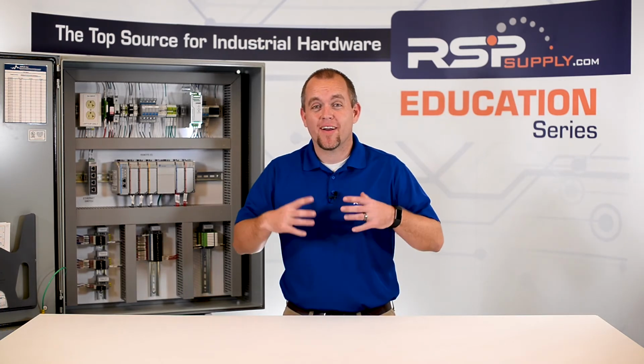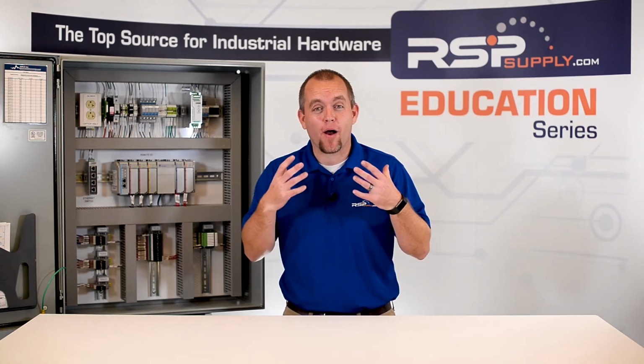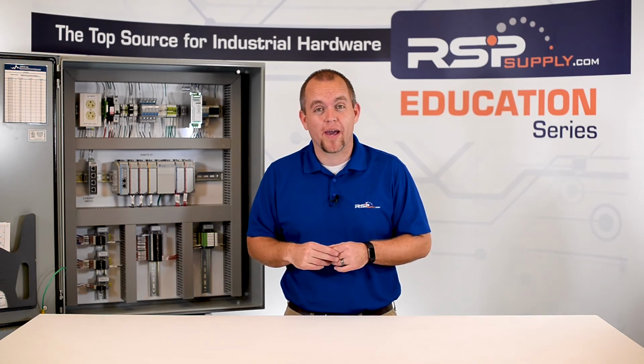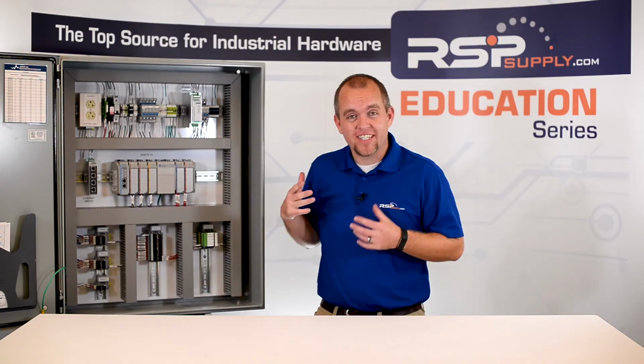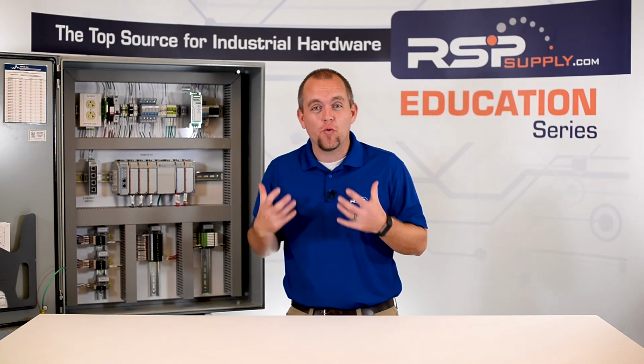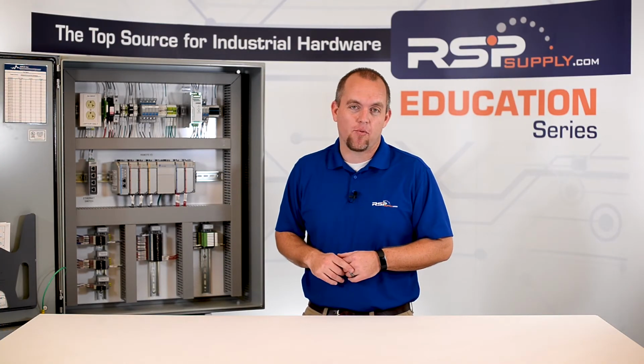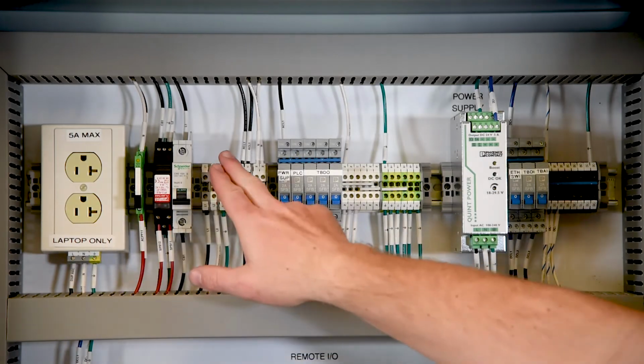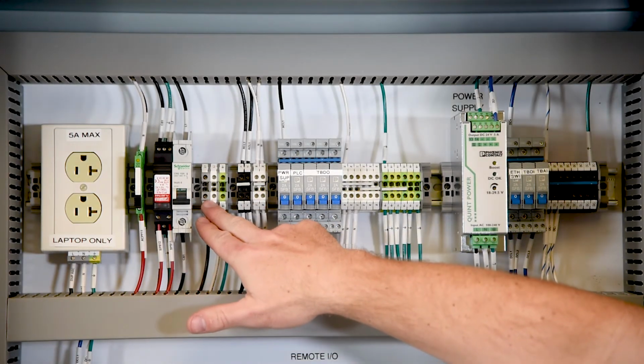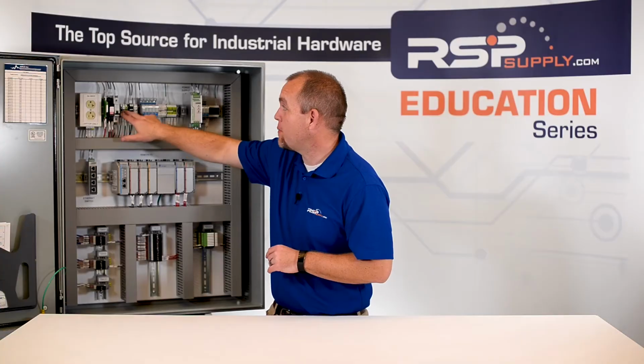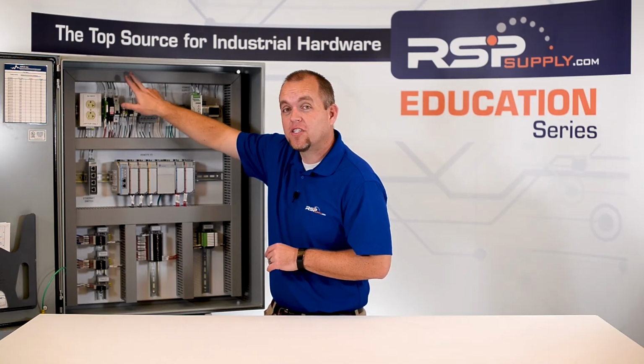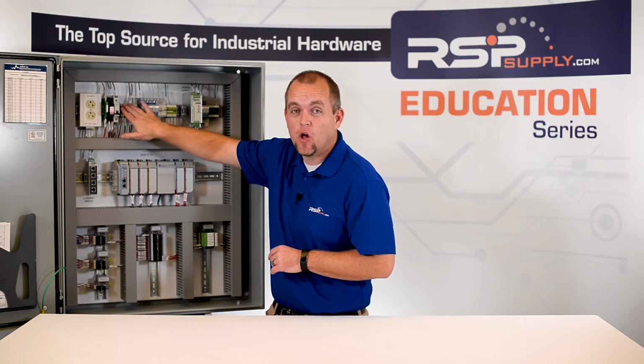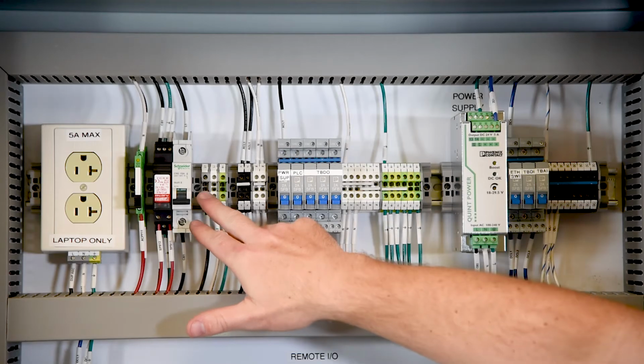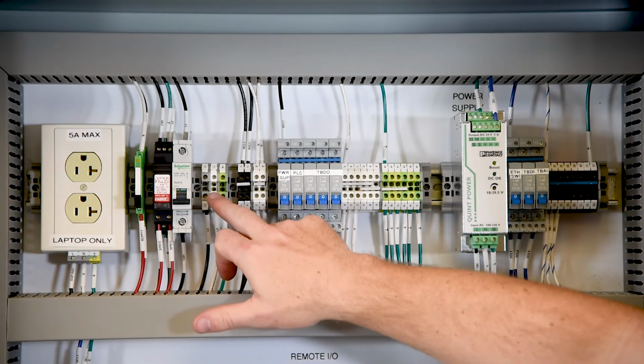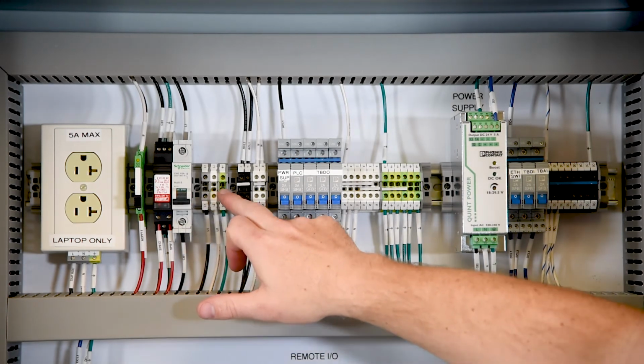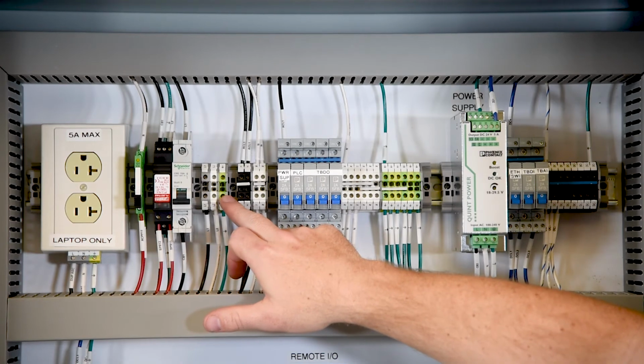So now that we've talked about several different topics regarding power distribution within an industrial control panel, let's take you through this panel step by step and show you what the power is doing, where it's going, and how it's operating. First, we're going to have main power coming into our panel right to these terminal blocks. Again, the power is going to be coming at the top of the panel, so we have the power distribution located at the top of the panel. We have main AC power, in this case 120 volts, our neutral, and our main ground for the entire panel.